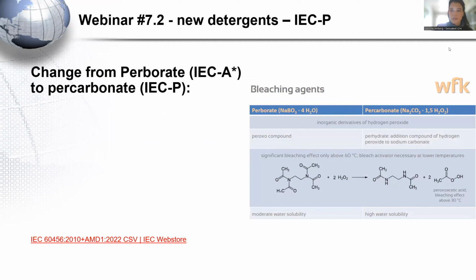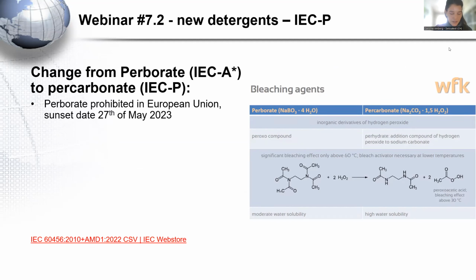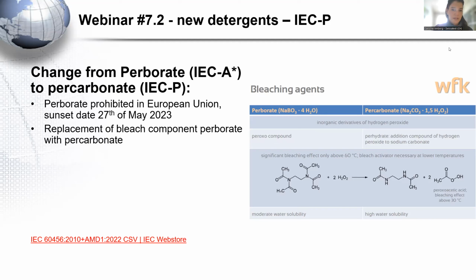Then, some words on this change from perborate to percarbonate. The reason for that is that perborate will be prohibited in the European Union from May on this year. So in the European Union, it will be prohibited to ship, to store, and to use perborate from this date on, and therefore it has to be replaced. But as I said before, the base powder composition stays completely the same. You will also see that on the label of this base powder, we have changed that to IEC-A*/P base powder, just to make it clear that it is still the same product.